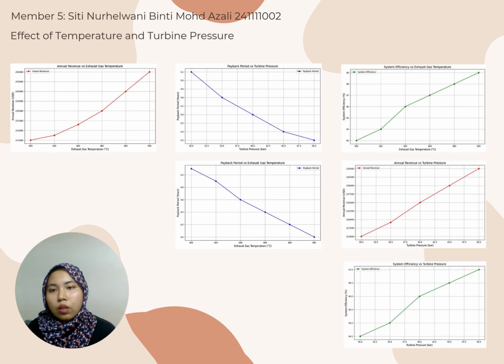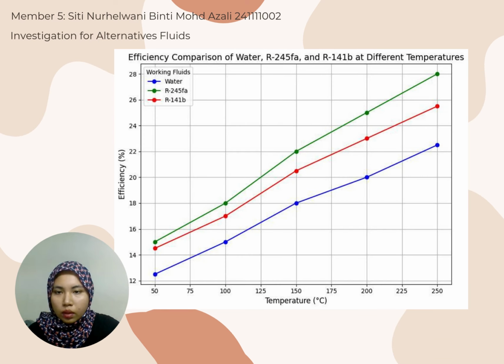This slide shows how exhaust gas temperature and turbine pressure affect the performance of the waste heat recovery system. Higher exhaust temperature and higher turbine pressure make the system work better. This increases power and water production, raises revenue, and helps recover the cost faster. This graph compares the efficiency of water, R245FA and R141B at different temperatures. As temperature increases, efficiency also increases for all fluids. R245FA performs the best, especially at low temperature, and R141B performs better than water and works well at medium temperature.